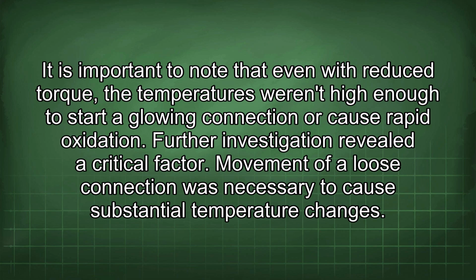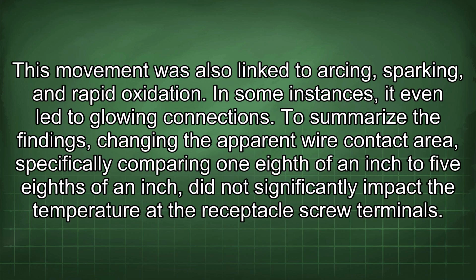or cause rapid oxidation. Further investigation revealed a critical factor. Movement of a loose connection was necessary to cause substantial temperature changes. This movement was also linked to arcing, sparking, and rapid oxidation. In some instances, it even led to glowing connections.